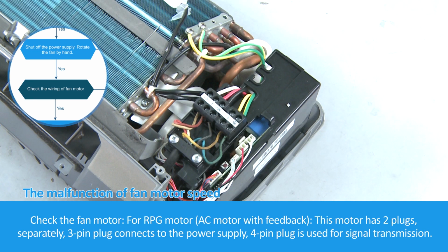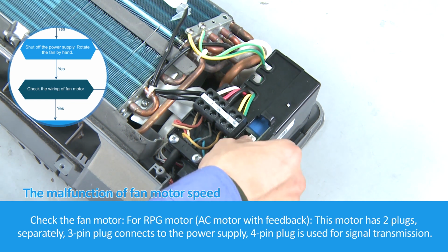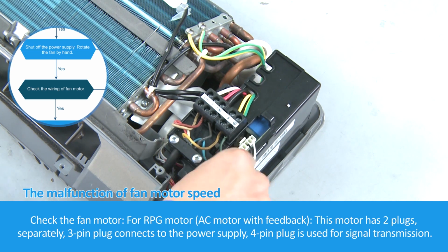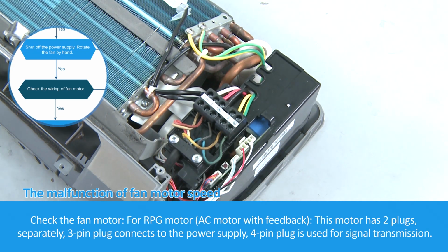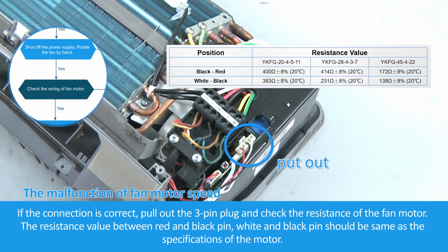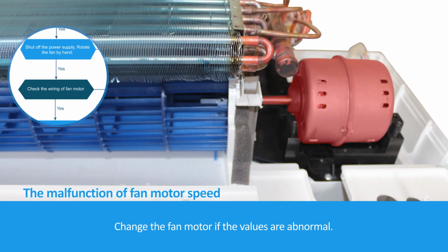Check the fan motor for RPG motor, AC motor with feedback. This motor has 2 plugs separately: the 3-pin plug connects to the power supply, and the 4-pin plug is used for signal transmission. If the connection is correct, pull out the 3-pin plug and check the resistance of the fan motor. The resistance value between red and black pin, and white and black pin should be the same as the specifications of the motor. Change the fan motor if the values are abnormal.